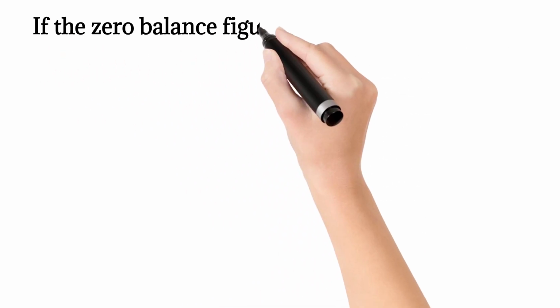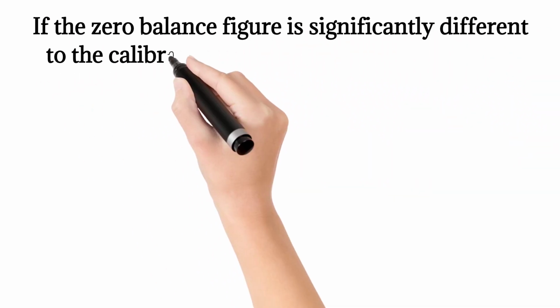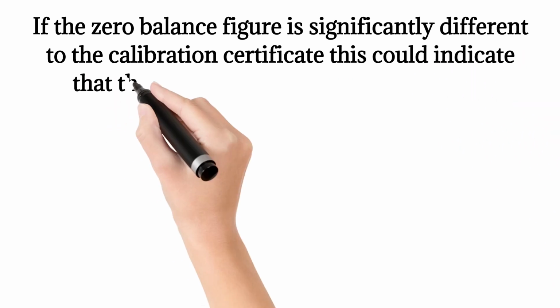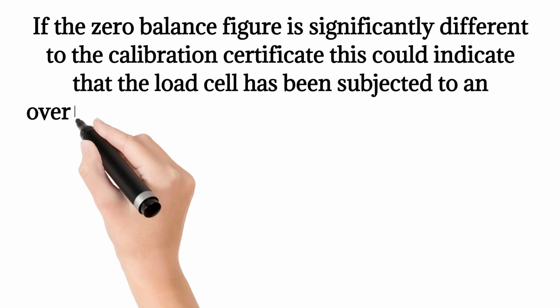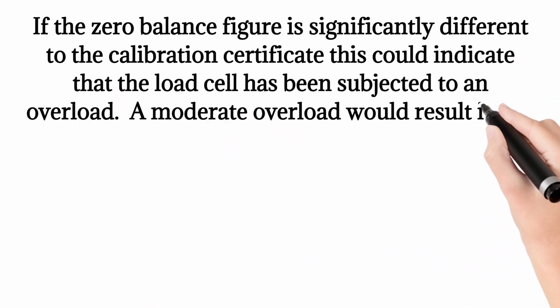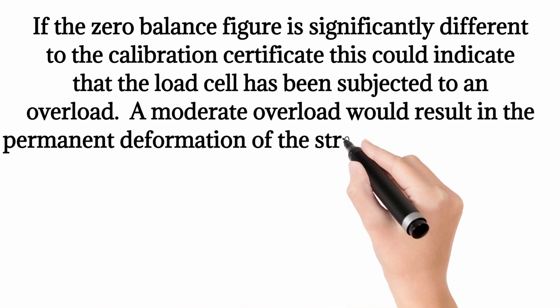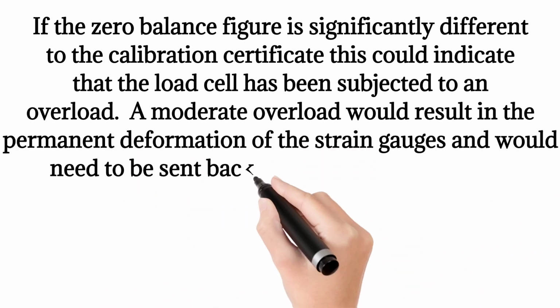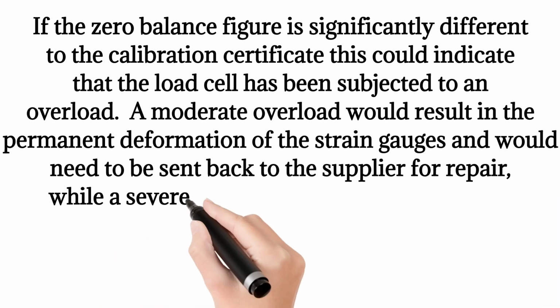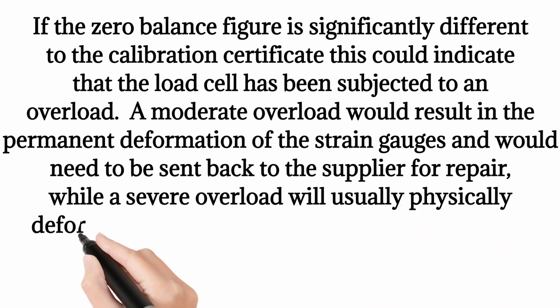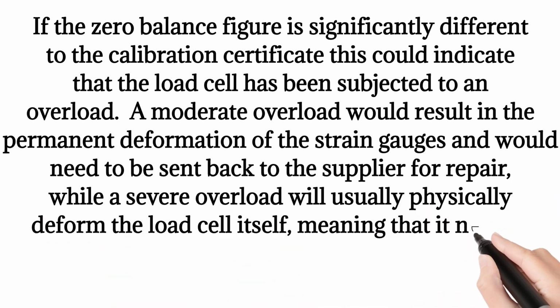If the zero balance figure is significantly different to the calibration certificate, this could indicate that the load cell has been subjected to an overload. A moderate overload would result in the permanent deformation of the strain gauges and would need to be sent back to the supplier for repair, while a severe overload will usually physically deform the load cell itself, meaning that it will need to be replaced.